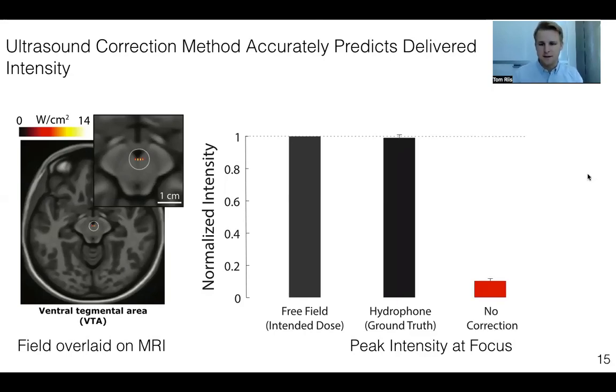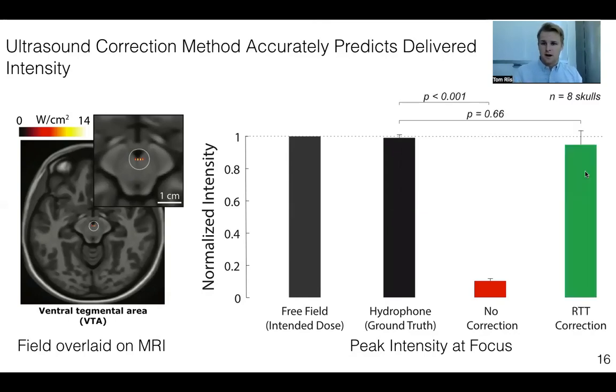This is the intensity at target when no correction is applied. So again, we reduce the intensity at target by roughly an order of magnitude, and it's highly variable across subjects. And I want to point out that this is actually what's often done in the field with human subjects. And finally, this is the result of our ultrasound-based correction method. We recover roughly 95% of the intended intensity at target.